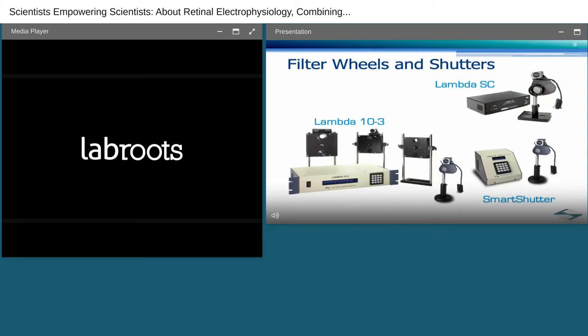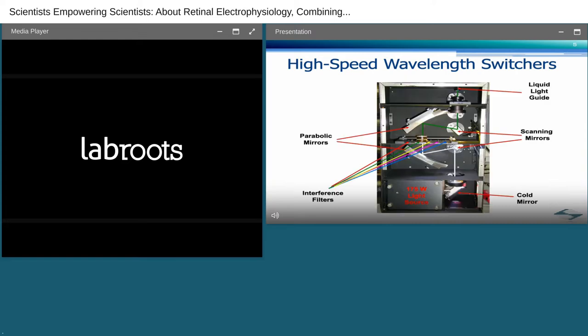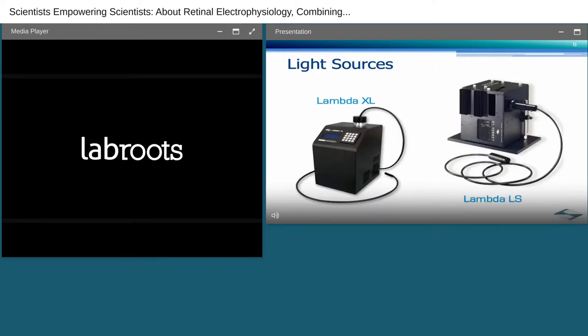Over 30 years ago, Sutter engineers set out to design a reliable, fast, electrically quiet, computer-controlled filter wheel. The result was the Lambda 10. As technology advanced in the field of imaging, so was demand for faster wavelength switching speeds than the filter wheel could provide. Sutter introduced the Lambda DG4. The DG4 was a complete illumination system, offering speed and versatility for rapid wavelength switching in less than a millisecond. This high-speed switching was achieved by using dual-scanning mirrors mounted on galvanometers directing the light through interference filters for wavelength selection.